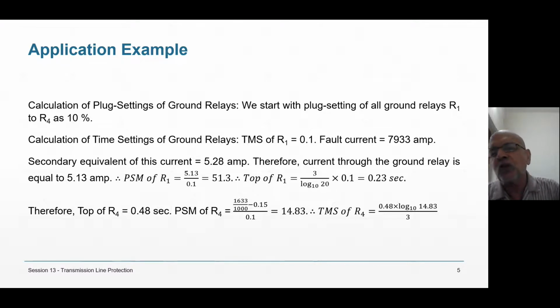So we start with plug setting of ground relays R1 to R4 as 10%. Just like that only. I'm just guessing. You see, discriminatory, I have no ground to decide anything. But lowest I'm deciding. Lowest means the relay will operate as fast as possible. That I'm taking care of, because 10 to 40% is the setting. I'm deciding 10%, the lowest. Now fault occurs near R1. So TMS of R1 I am assuming 0.1.